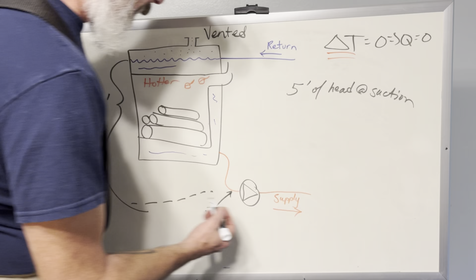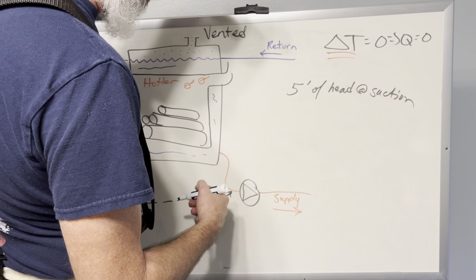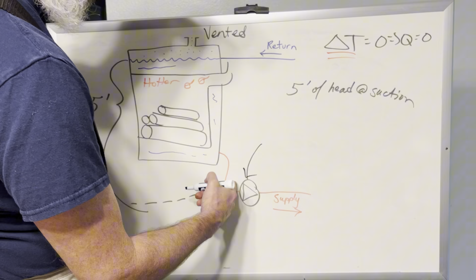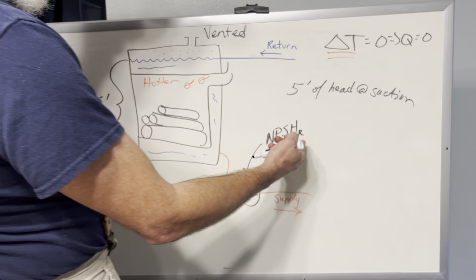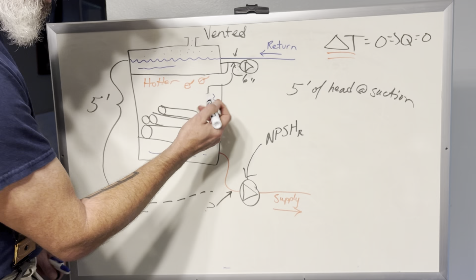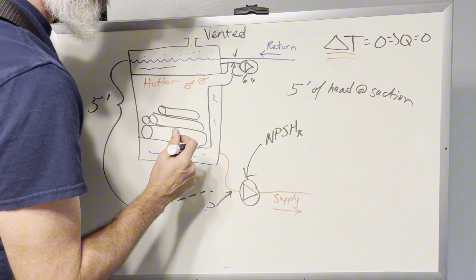But it's important because every pump from every manufacturer on the planet will have a requirement for the inlet side, or the suction side, and that is NPSH. You can denote it R, but that's net positive suction head required. Well, you may not have that net positive suction head available if you pull it from up here. If you pull the pump from here, and let's say that's 6 inches, that distance where the pipe's coming out, if you pull from the top, yeah, that water's hotter. It's definitely hotter, and that's why most people say definitely take it from the top, because it's the hottest water. Yeah, but how much head is over that pump? Meaning there's only 6 inches of water. So that's 6 inches of head at the suction.